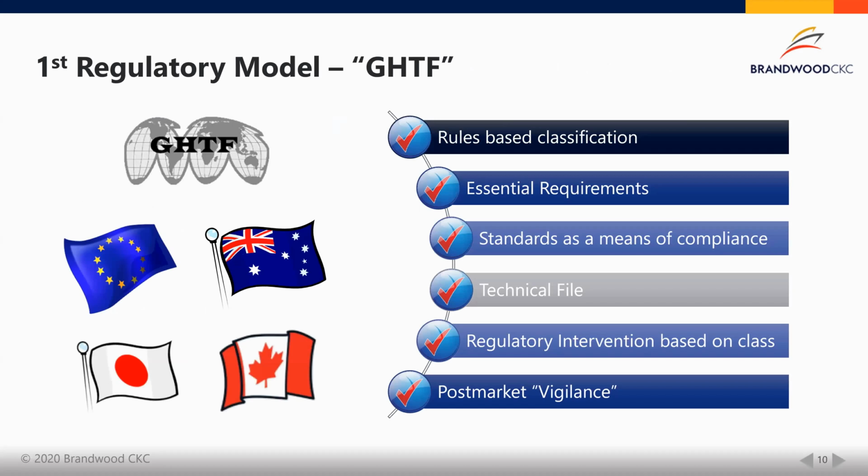So as mentioned in the agenda slide, there are two regulatory models that I will be talking to you about today. The first is the GHTF model. GHTF is the Global Harmonization Task Force, which was a group that involved many countries and their regulatory representatives, and their goal was to harmonize regulation around the world. This group doesn't exist anymore, they've disbanded, and it's now known as the International Medical Device Regulators Forum. But it's still called the GHTF model, as they were the original group that organized this.